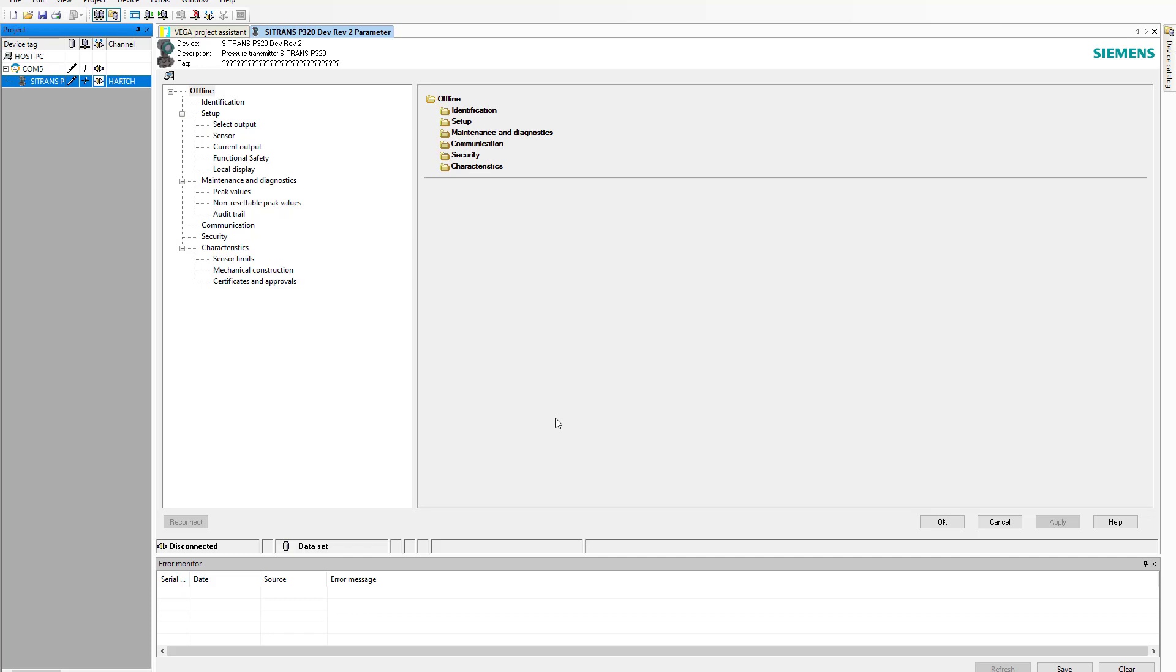So that's it. Importing the device into PACTware. Just be careful. When it's a Siemens device, we need to install SITRANS DTM. If it's a standard DTM, and Vega are pretty good at this, they don't do this conversion in the background. You just have a standard DTM install. Then you don't need that. You only need SITRANS DTM for Siemens SITRANS instruments.